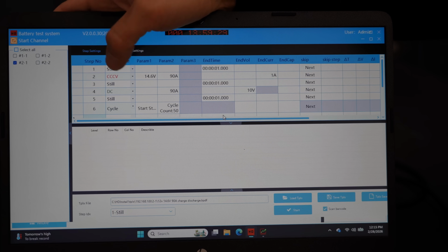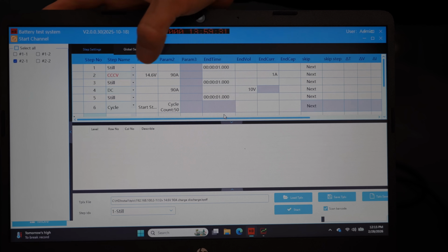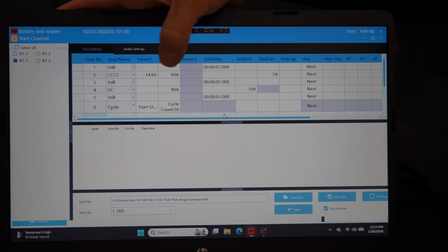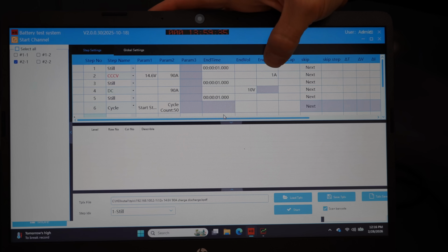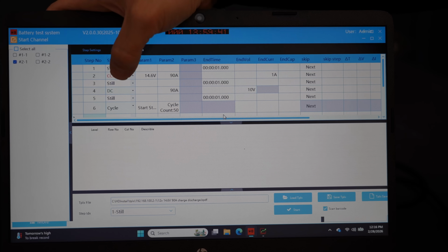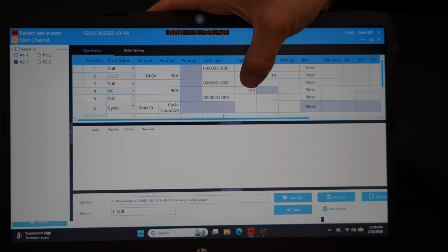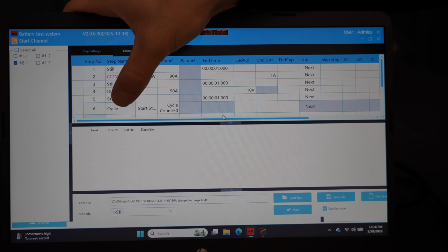Step number 2 is constant current, constant voltage up to 14.6 volts at 90 amps until the end current is 1 amp, and then the battery is fully charged. Then pause for 1 second, then discharge at 90 amps until it goes down to 10 volts. Then pause for 1 second, but you can change this obviously, and then cycle. So we will do this cycle 50 times.